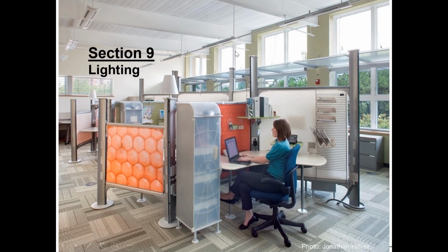These are, of course, south-facing glazing with exterior shading and exterior light shelves, and this is an interior light shelf. So the light can bounce off the light shelf. It almost looks reflective, but it is actually opaque. The light hits it, bounces off the light color ceiling, and you can kick natural daylight deep into the space. And as a result, these lights are turned off.